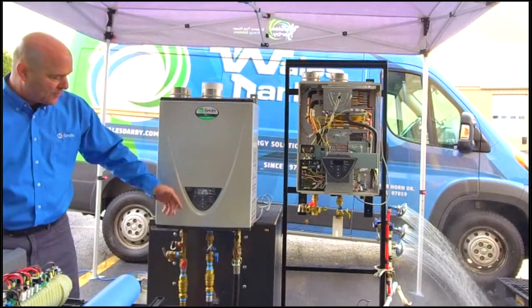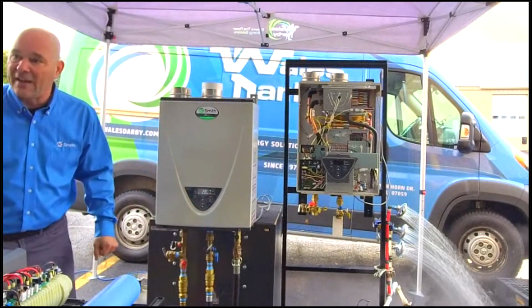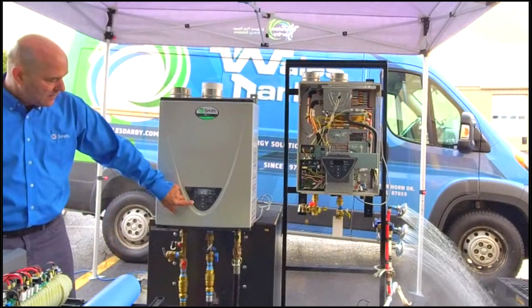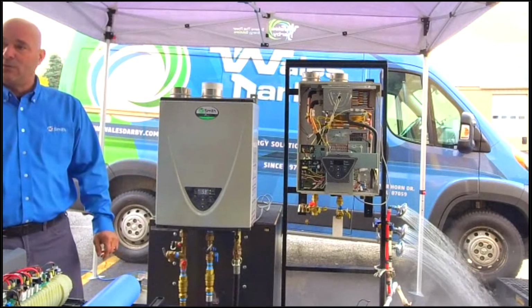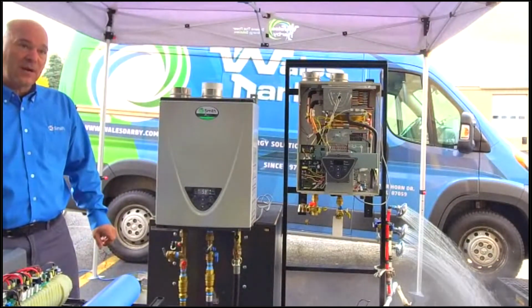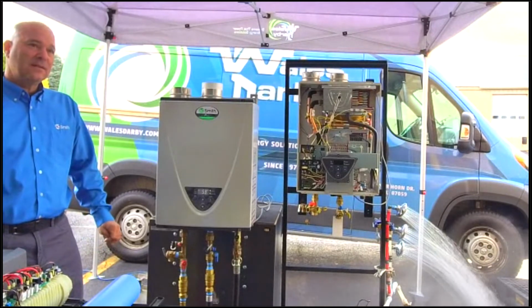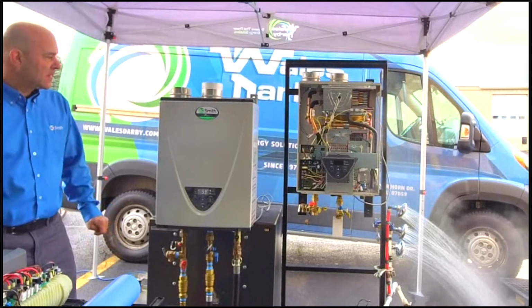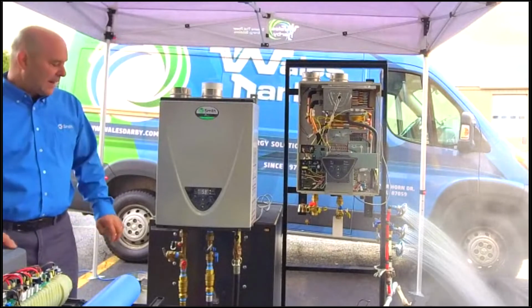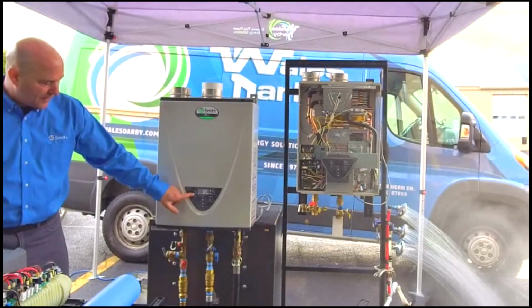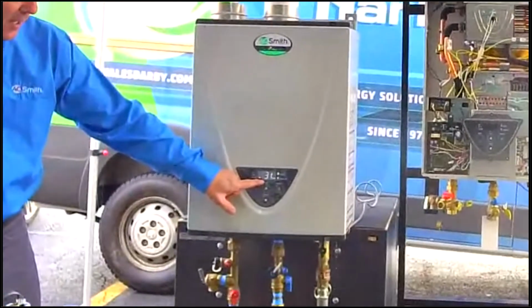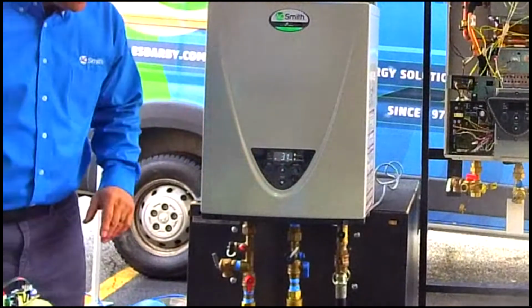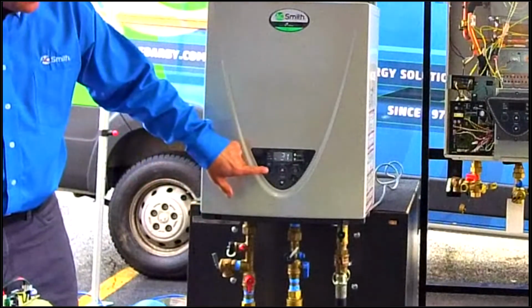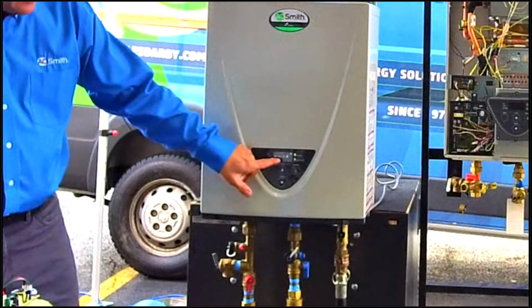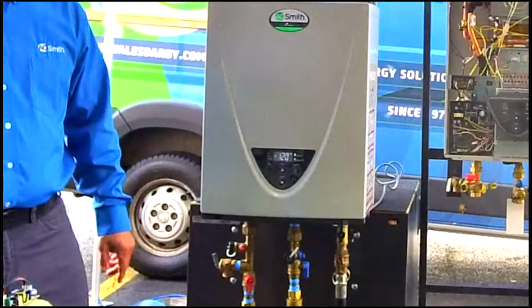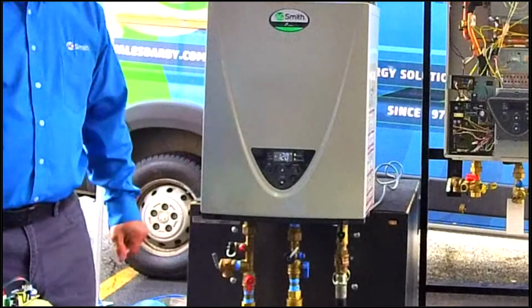Let's see if I can get any higher flow rates right now, 2.7. Again, we could get up to 5.9 gallons per minute right now because of the 53-degree inlet water temperature. Rob, any questions there while we're fired up and running? Not regarding that, no, but there is, actually, hold on one second, we have one. GPM is shown on the screen when in operation. That is correct. GPM will be shown on the screen, and it's called on here flow. I'm at 3 gallons per minute right now of flow, 3.1. That means somebody's not using water in the building right now, which is good because we're getting higher flow rates, and we're still easily maintaining 53-degree inlet and 119, 120-degree outlet water temperature right now. So yes, it will always be predicated on, do I see a demand?